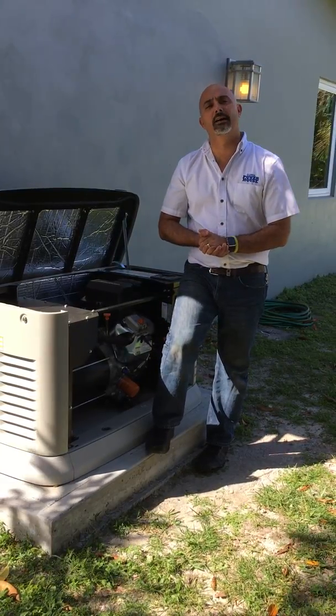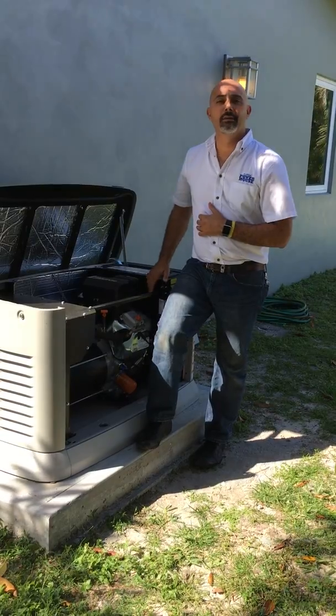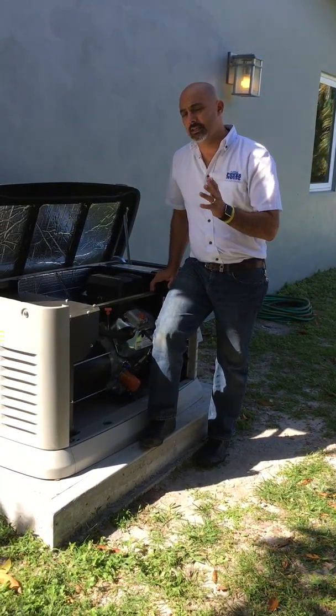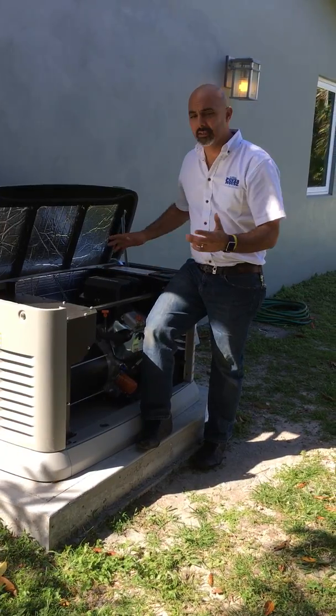The fifth — and by the way, a funny one — is the generator being left in the off position. If you want the generator to work, you've got to have it on auto. It's simple.